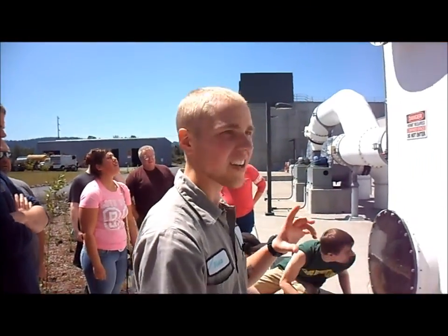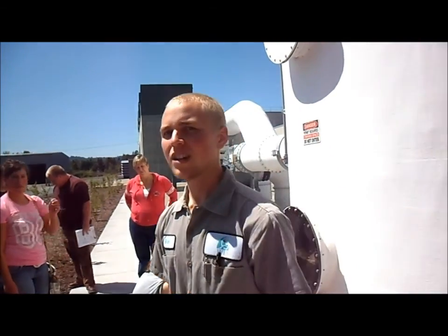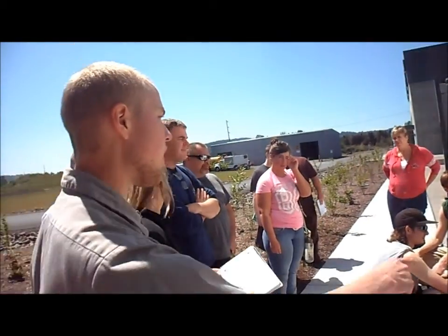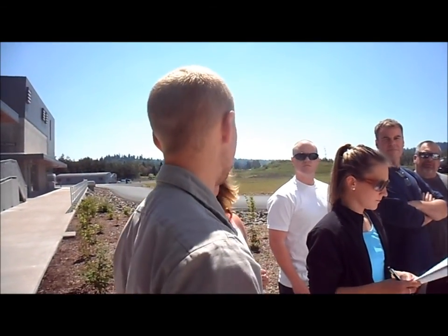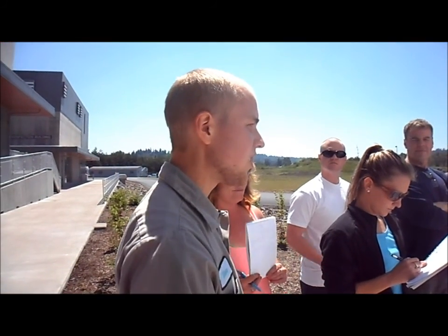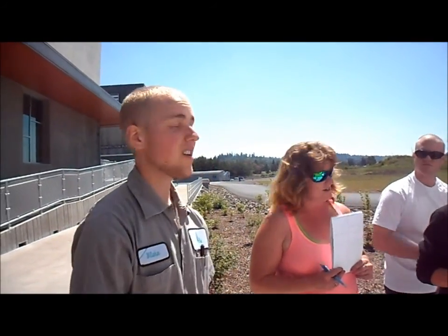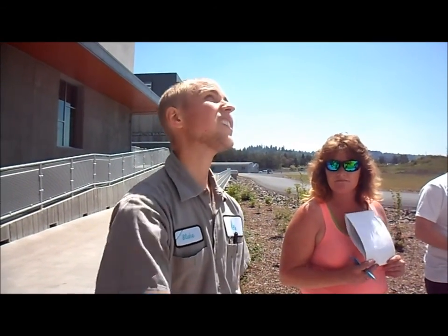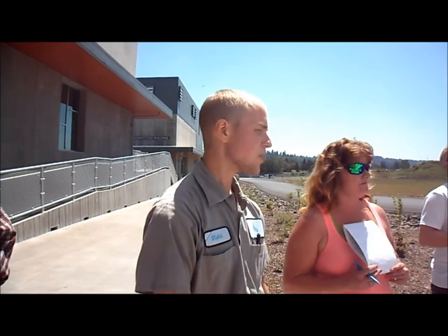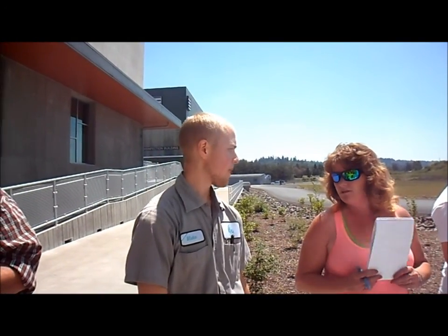Beds like that look like a sponge, and we're pumping odorous air through the bottom, and then we're trickling water down from the top with nutrients in it. It looks like Miracle Gro, and the bugs take care of all the odorous air. We have a nutrient tank, we just add a little Miracle Gro, and it comes in at the top. This is W3 water.